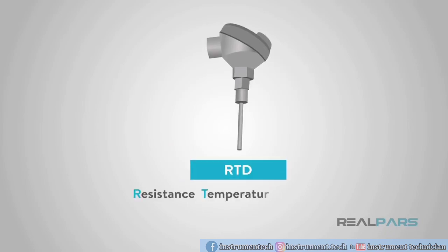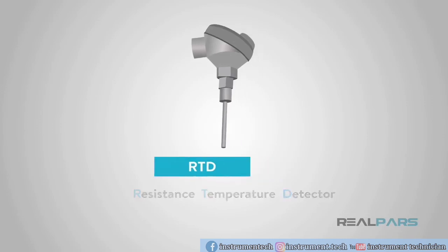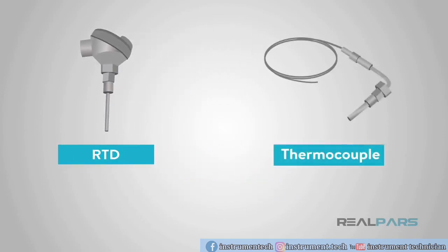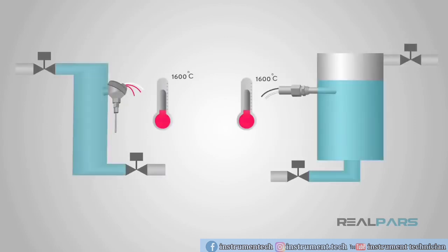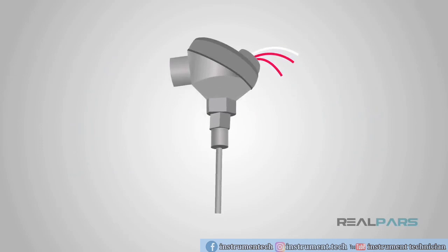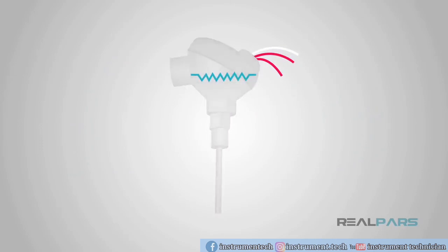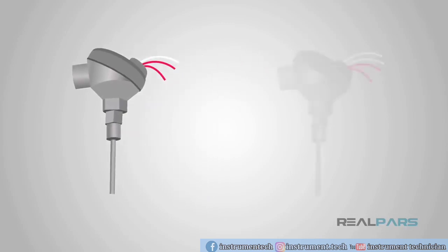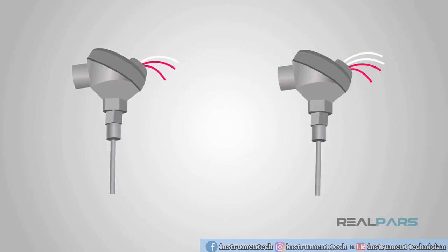RTD, or resistance temperature detector inputs. The newer RTD, or resistance temperature detector, is generally more robust and accurate than the thermocouple, but the older sensors are still quite common because they are both designed into older equipment and capable of operating at temperature ranges that RTDs are not made to handle, including up to white heat, 1600 degrees Celsius, in unique applications. As the name implies, the resistance of the device changes with its temperature, so measuring the output is relatively straightforward. They generally come in 3 and 4 wire configurations and several temperature ranges.